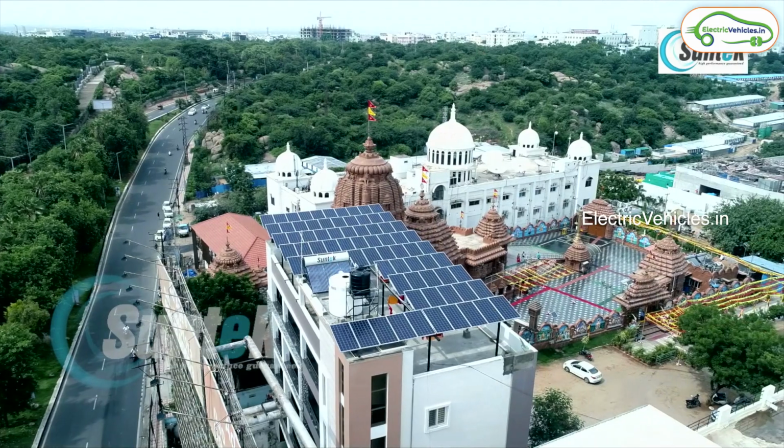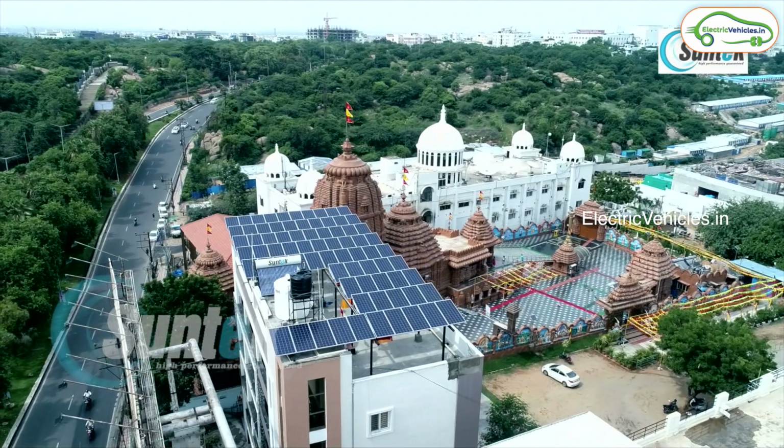Facing south. Usually, in 1 kilowatt, how many solar panels do we get? As I said, 335 watts is the standard for subsidy, because only Indian-made cells are eligible for the subsidy. Most residential systems we install come with 335 watt panels at maximum. So 3 panels are used in 1 kilowatt, and if we take 3 kilowatts, we get around 9 panels.